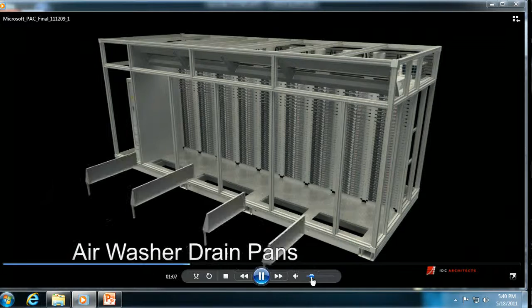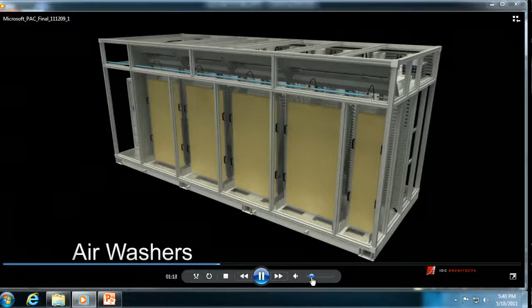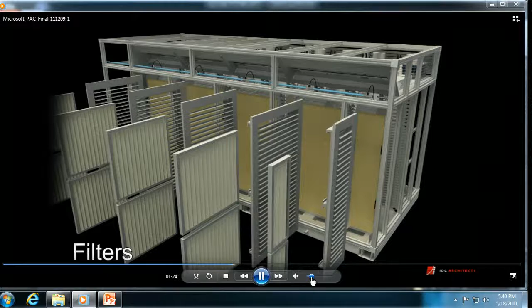So we have the same setup I told you about at Dublin — filters, washers, and the water flow system above. We'll put this under load in a second, introducing water only at the high end of the spectrum. The maintenance involves the air washers and filters, depending on what part of the world you're in — those need regular servicing. But this seals up, is fully outdoor rated, and can run anywhere. We've decided to put them in buildings, as I mentioned earlier.